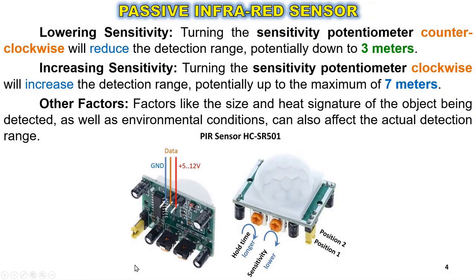If we want to detect short distance, like 3 meters, then we turn the sensitivity potentiometer counterclockwise. If we want to detect long distance, like up to maximum of 7 meters, then we turn the sensitivity potentiometer clockwise. However, factors like the size and heat signature of the object being detected, as well as environmental conditions, can also affect the actual detection range or distance.